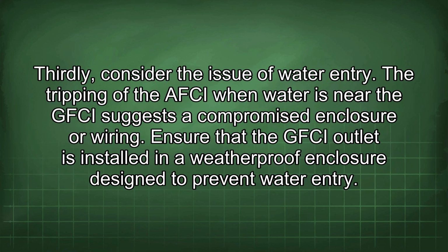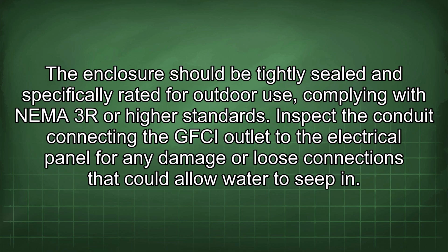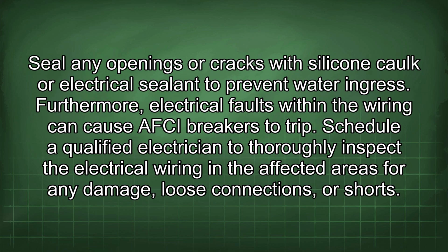Thirdly, consider the issue of water entry. The tripping of the AFCI when water is near the GFCI suggests a compromised enclosure or wiring. Ensure that the GFCI outlet is installed in a weatherproof enclosure designed to prevent water entry. The enclosure should be tightly sealed and specifically rated for outdoor use, complying with NEMA 3R or higher standards. Inspect the conduit connecting the GFCI outlet to the electrical panel for any damage or loose connections that could allow water to seep in. Seal any openings or cracks with silicone caulk or electrical sealant to prevent water ingress.